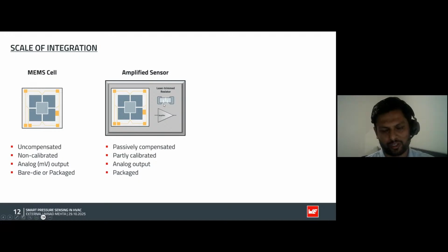During production, at 25 or 30 degrees, we correct the values so they are stable and calibrated for certain temperatures. If factory calibration is done at 25 degrees and your end application works at 60 degrees, it's very possible the output at 60 degrees won't be fully calibrated like in the lab at 25 degrees. So this is a better solution in terms of calibration.